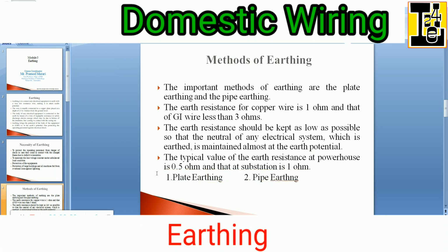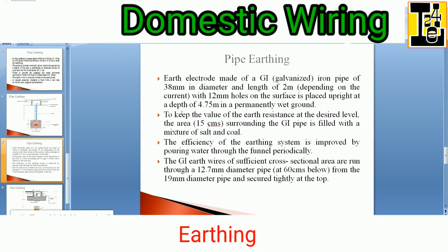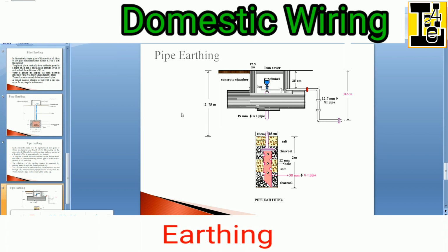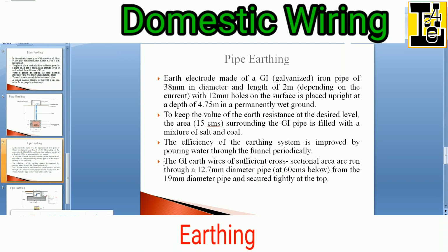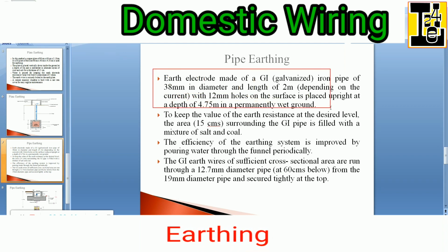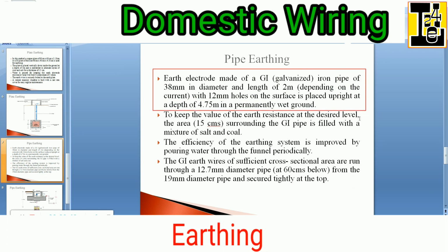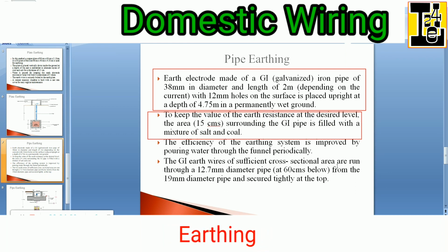Let us go one by one. I shall first discuss pipe earthing. This is the figure. You can observe the pipe earthing over here. I shall give an explanation for this. The earth electrode is made of GI, or galvanized iron. A GI pipe of 38 mm in diameter and length of 2 meters, depending on the current, with 12 mm holes on the surface, is placed upright at a depth of 4.75 meters in permanently wet ground. To keep the value of earth resistance at the desired level, the area 15 centimeters surrounding the GI pipe is filled with a mixture of salt and coal.